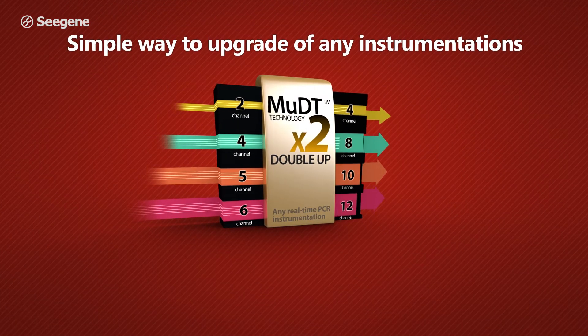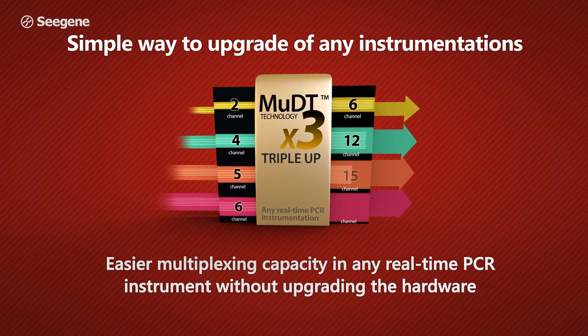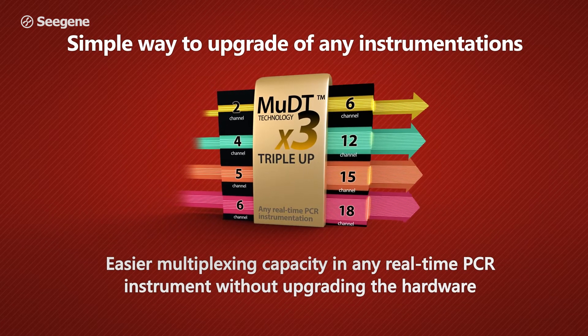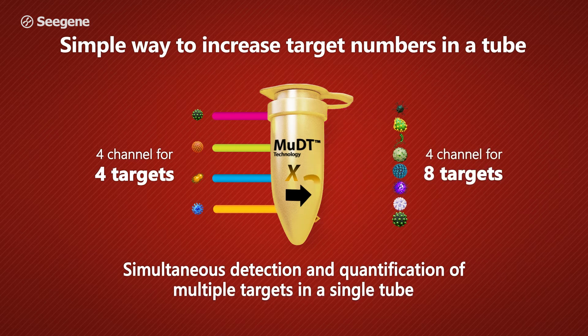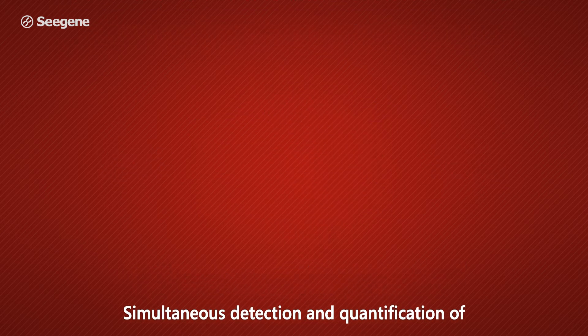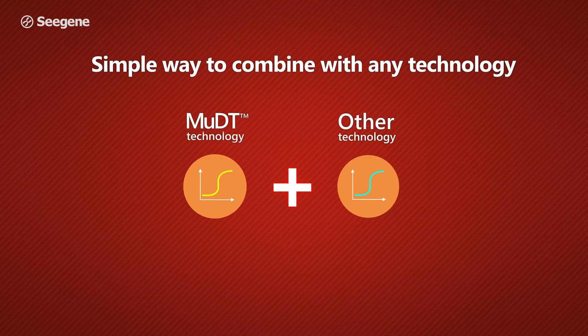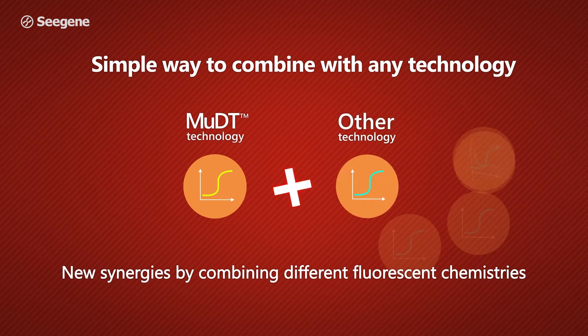MUDT increases the multiplexing capability of any existing real-time PCR instrument without requiring new hardware. MUDT increases the target numbers in a tube up to three times while still providing superior quantitative CT information. MUDT works with any fluorescent chemistry, opening new possibilities for the molecular diagnostic industry.